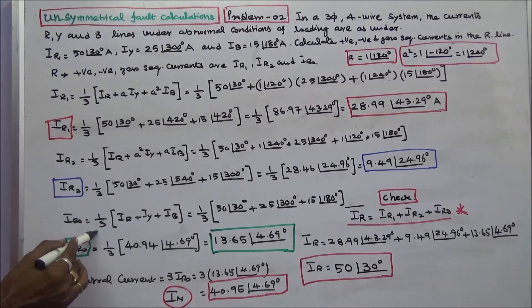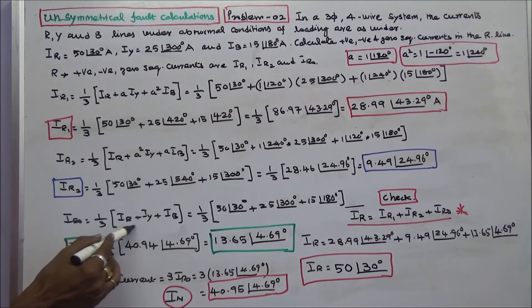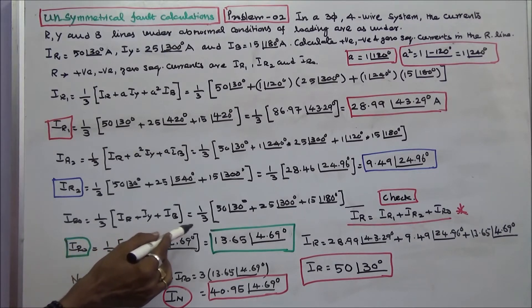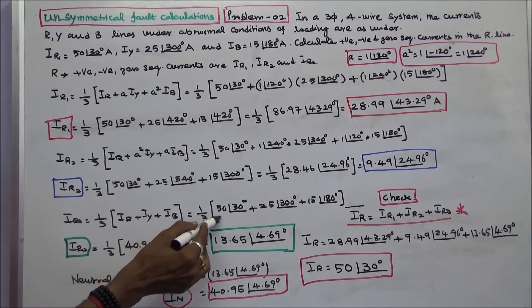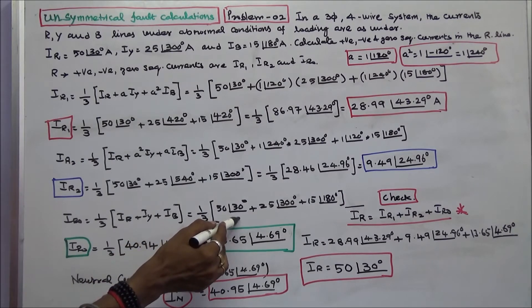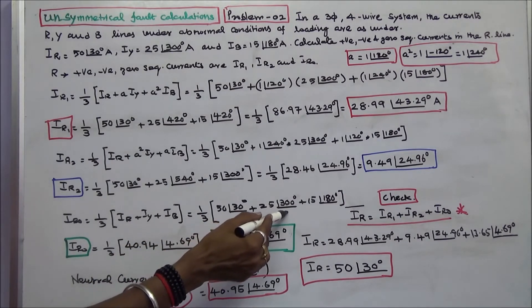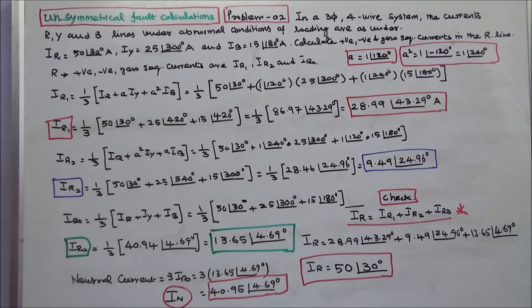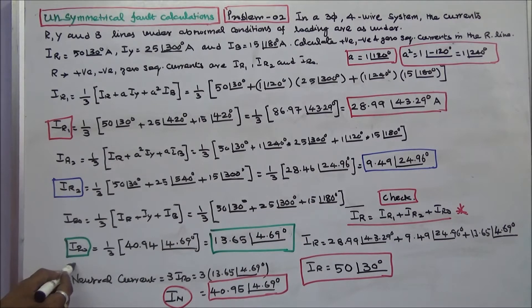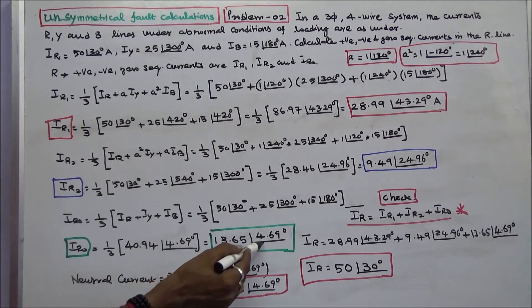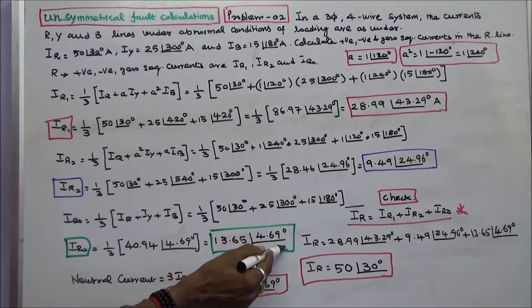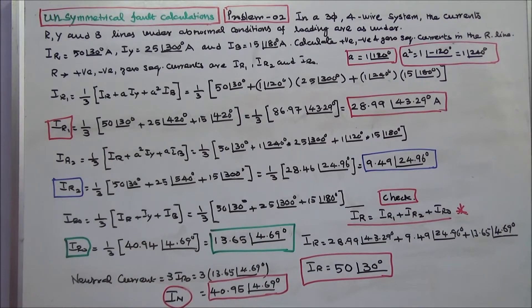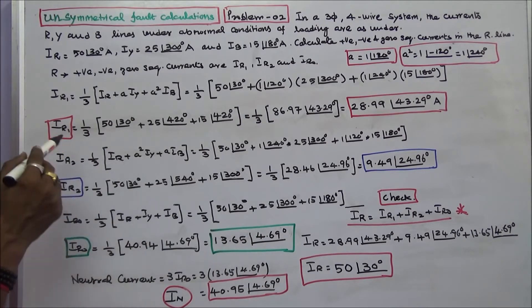The zero sequence current IR0 is equal to 1/3 into (IR + IY + IB). That is equal to 1/3 into [50 angle 30 degrees + 25 angle 300 degrees + 15 angle 180 degrees]. Zero sequence current IR0 is equal to 13.65 angle 4.69 degrees.